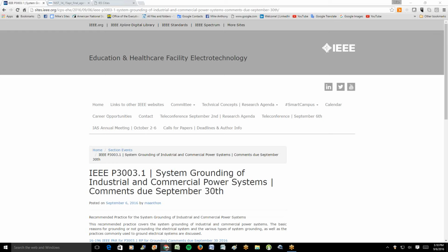What is the perspective of the University of Alberta system, which is what? It's about a 50 megawatt system over there you've got? Or MVA? Well, it runs at about 50 on average. I would say it's a 90 MVA capacity system. We've hit 76 MVA, and our nominal voltage is 13,800 volt. We have not implemented neutral grounding.